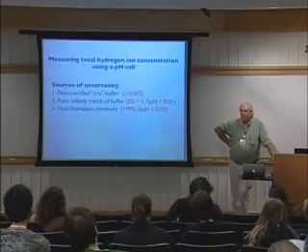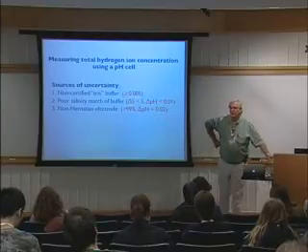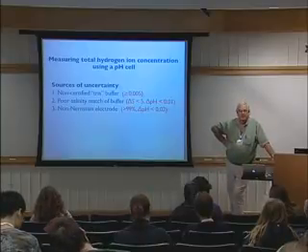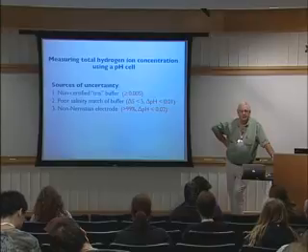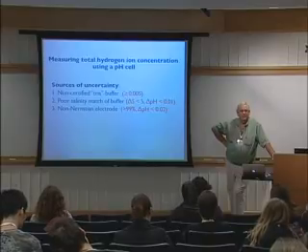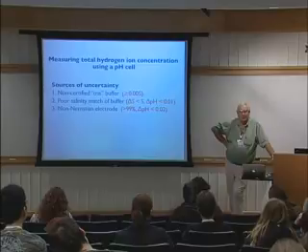If your electrodes are non-Nernstian? Well, if it's pretty good, 99% Nernstian, then the error in pH is always over the usual range, like 7.5 to 8.5, going to be less than 0.02. How would you know it's 99% Nernstian and not 75? Well, you know, your pH 4 and 7 buffers might tell you that reasonably, because that's supposed to be 180 millivolts. So, you know, you'd be almost 2 millivolts different.